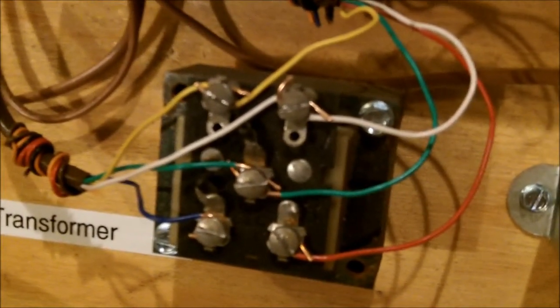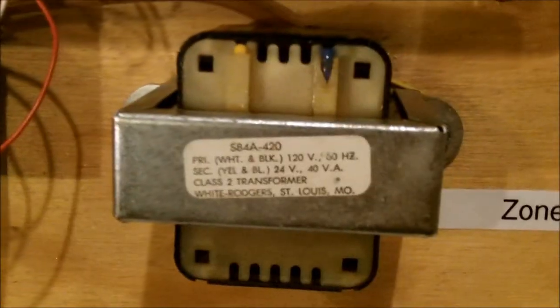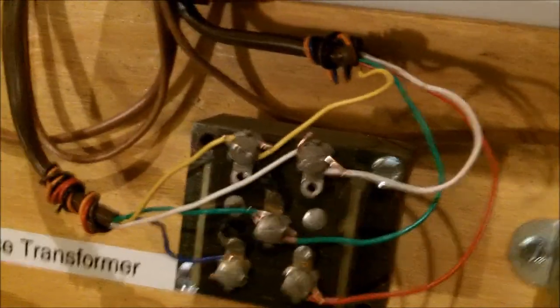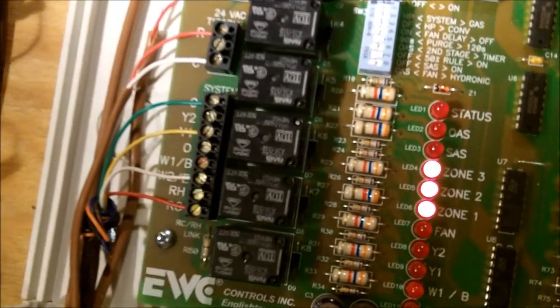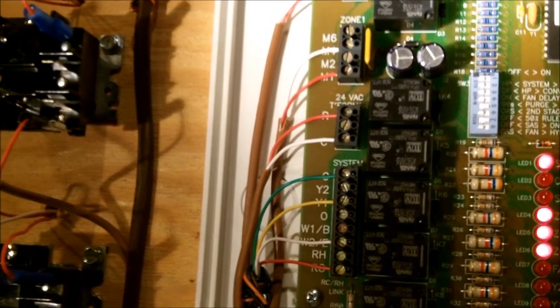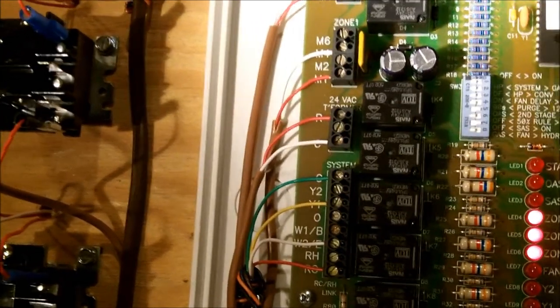The transformer down here is just my simulated blower compartment where all your electrical connections are. What I did is I have some old furnaces out there in my scrap yard, and so I just got a transformer from it, and for the zone panel I got a transformer for it. So of course your power is going to come down from Y1, and it's going to come down from G, come down through here at my wire connections. It's going to flow up the wire, and it's going to turn the contactor on, and it's going to send the signal over to the blower relay, and it's going to turn the blower on. So we're just waiting on it to satisfy, or to turn the thermostats on.